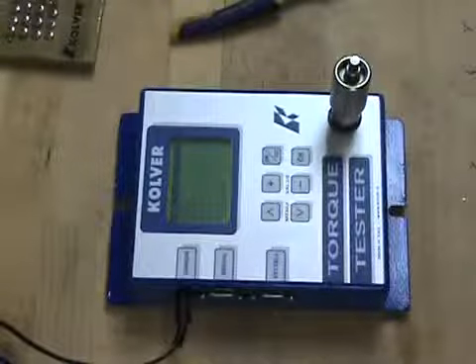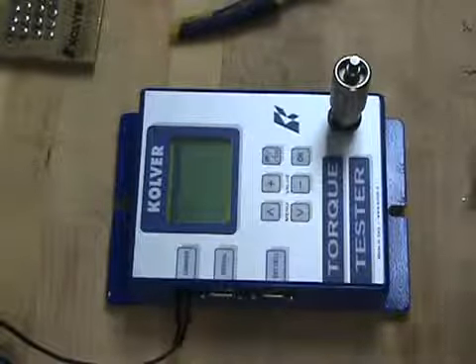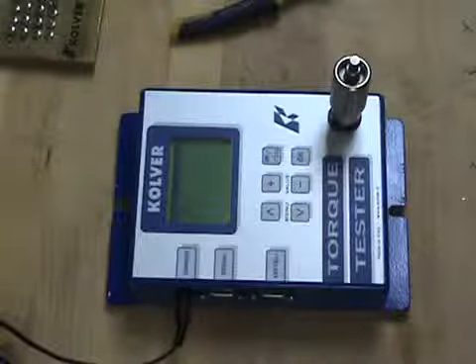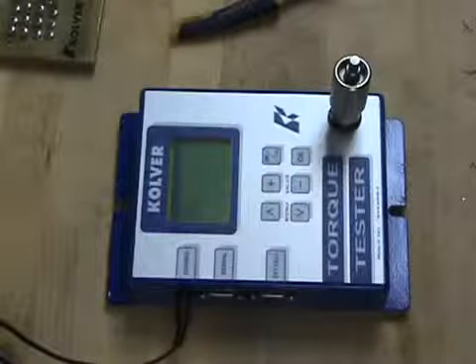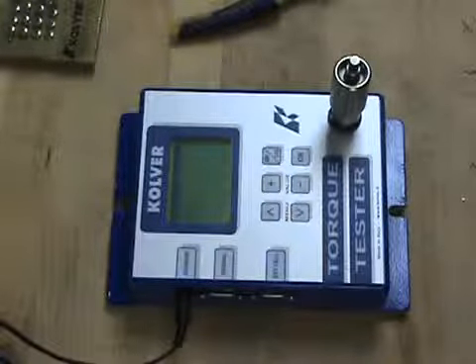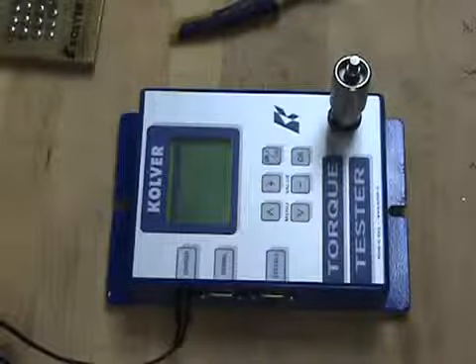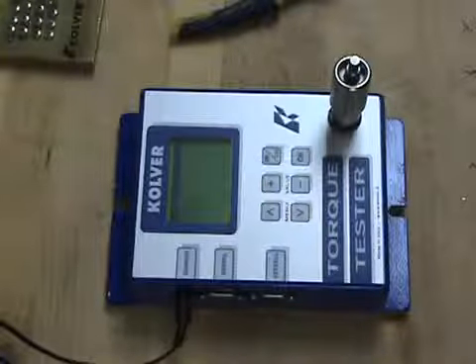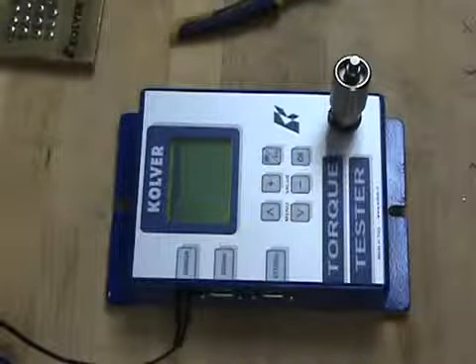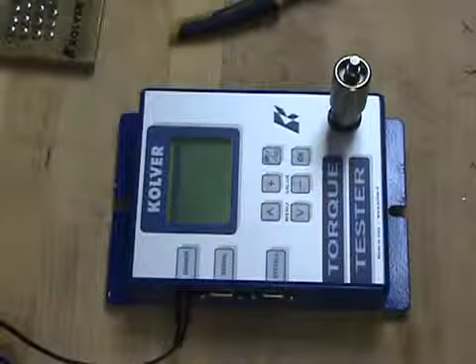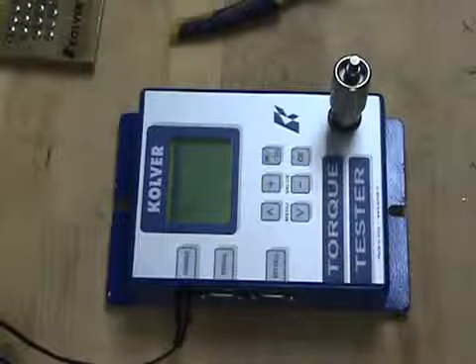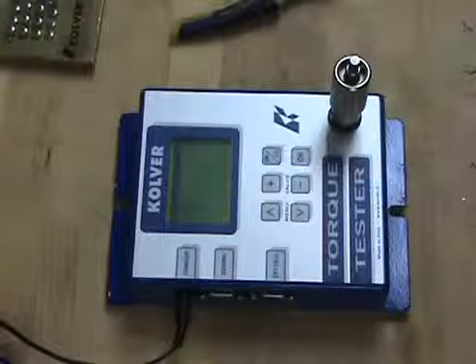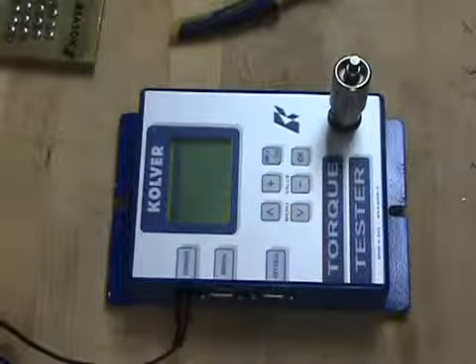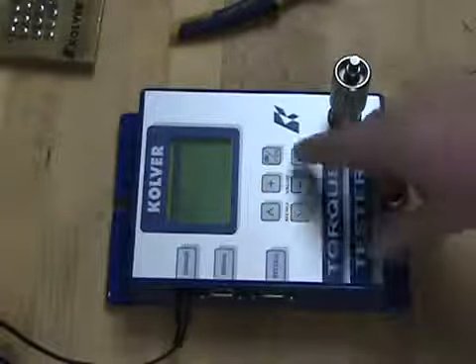If you go down to mode, you'll see we have peak, peak plus and peak minus, and then tracking. Peak plus is a maximum reading in the clockwise direction. Peak minus is your maximum reading in the counterclockwise direction. And track is live data, so you're at all times reading whatever the transducer is actually seeing at that moment in time. And we can click OK or Escape to get out of that.